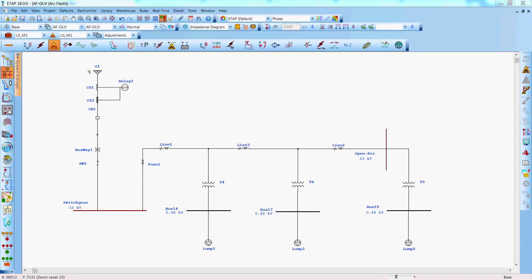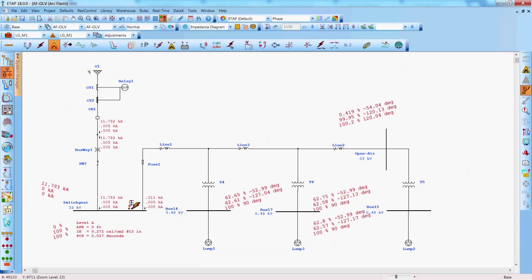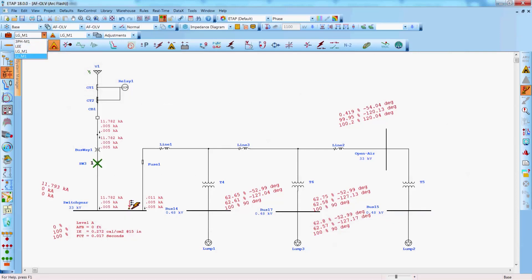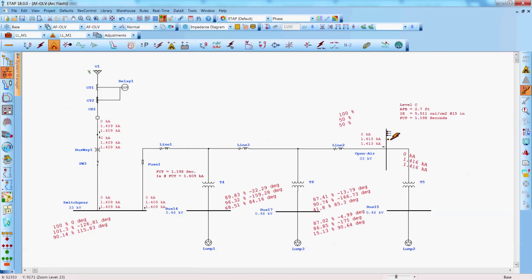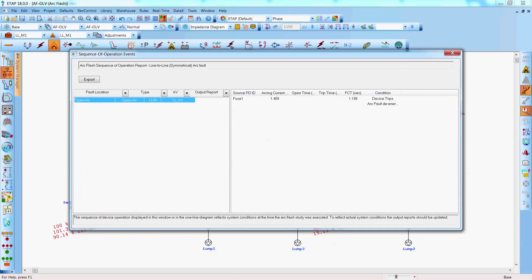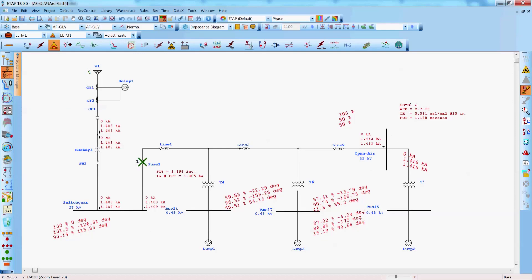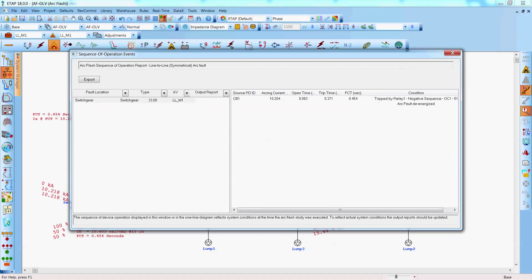Here is a quick demonstration of the sequence of operation for the high voltage arc flash module. You as the user can perform a sequence of operation, a quick simulation, and ETAP would provide not just the graphical view but also a comprehensive text report. This system definitely falls outside of the IEEE 1584 standard — all of these locations are well above 15 kV — and with this module you would be able to perform high voltage arc flash on those locations.